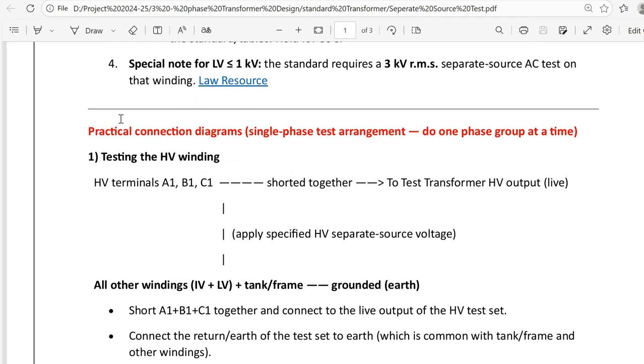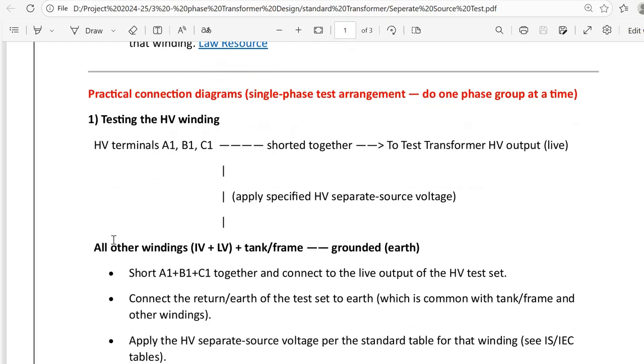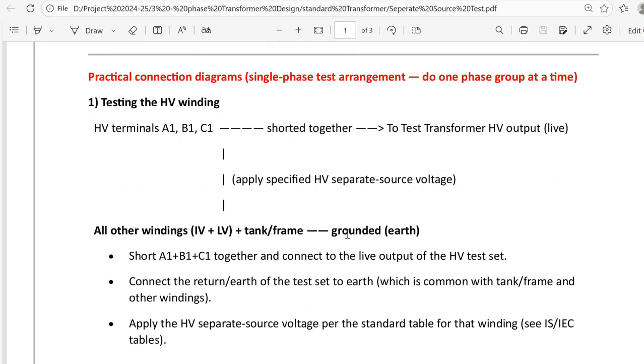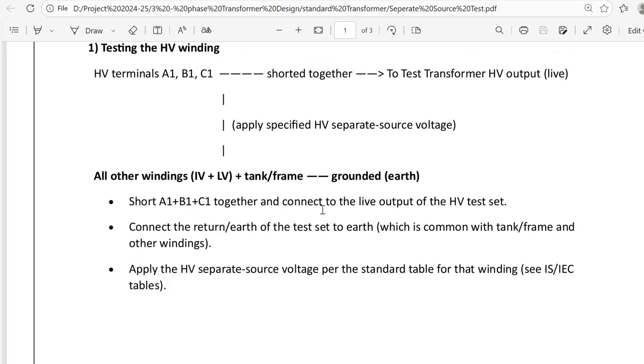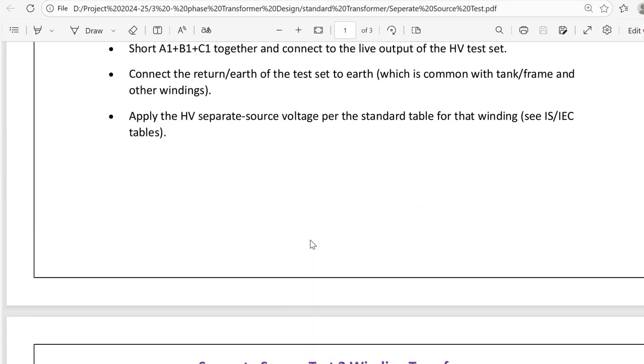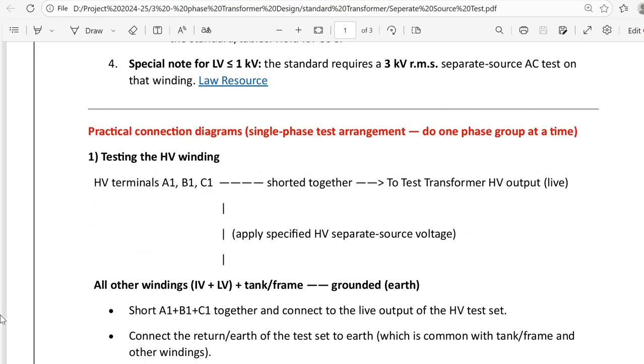This is the practical connection diagram, a single-phase test arrangement; do one phase group at a time. When testing the HV winding, HV terminals A1, B1, C1, meaning R, Y, B phase, are shorted together and connected to the test transformer HV output live. Apply the HV separate source voltage, and all other windings, like the LV winding, and the frame are grounded together. Connect the return earth of the test set to the earth, and apply the HV separate source voltage as per the standard table for the winding, as per IS and IEC standards.